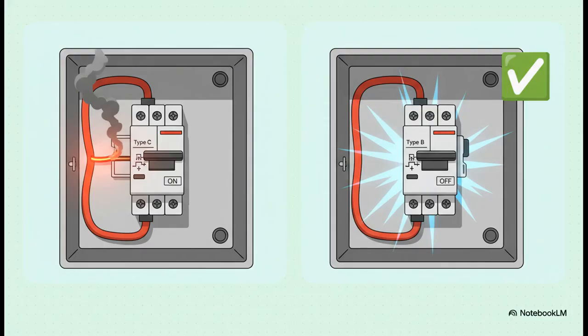Okay, this is where it all comes together. Let's focus just on the lights for a second. Imagine an electrician installs a Type-C breaker, that general-purpose one, on your lighting circuit. Here's the risk: because it's less sensitive, a short circuit might not create a big enough electrical surge to make that Type-C breaker trip instantly.